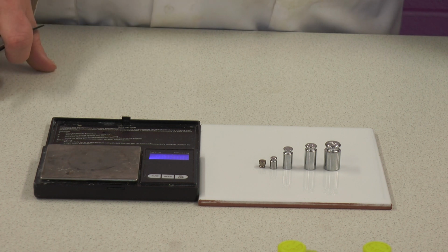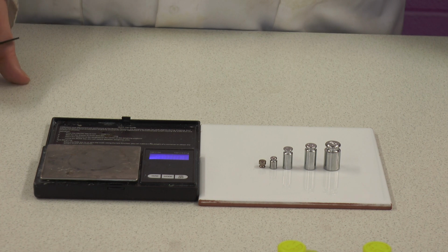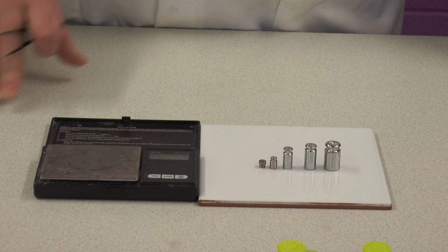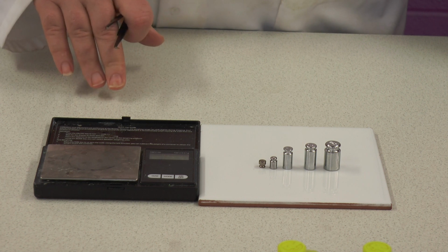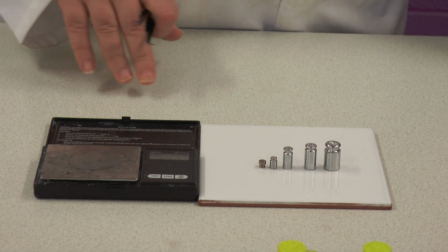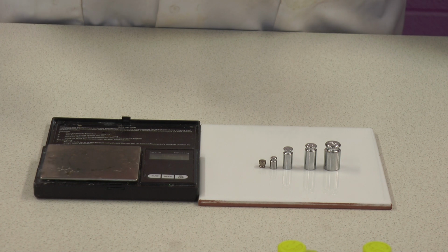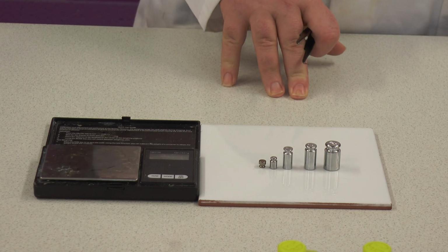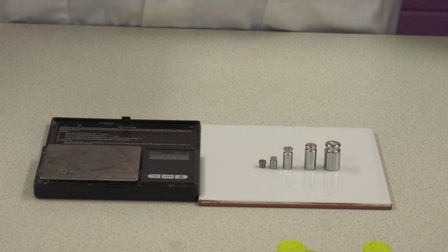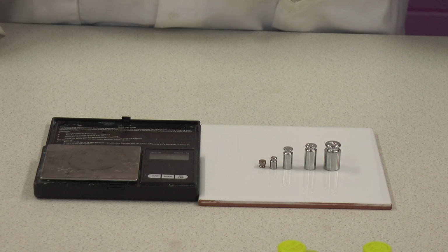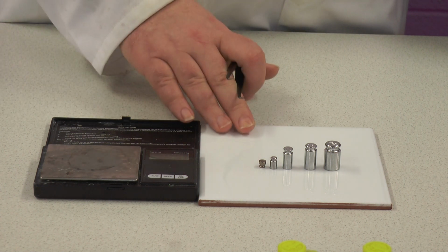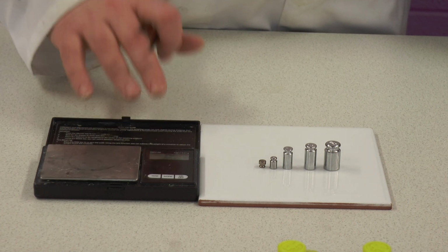If it wasn't linear, and this is where the graphs become very important, if, for example, one was added 0.01, but at 5, instead of it being 0.05, it might be 0.1 or 0.10. Sorry, 0.15. And then back at 20, it might have gone down again. And that's very bad news when a calibration isn't linear. So you've got enough readings there to have a go at drawing a graph, and therefore you can create a calibration graph for this balance.